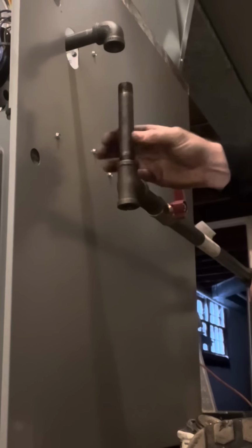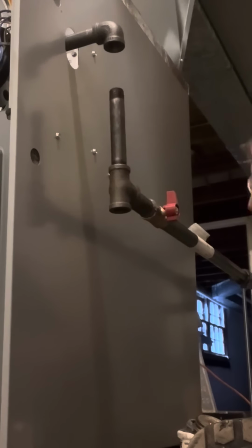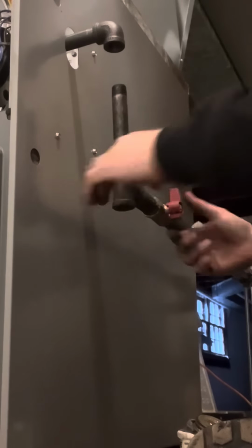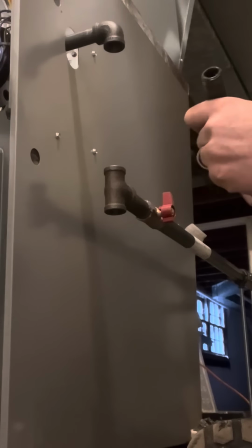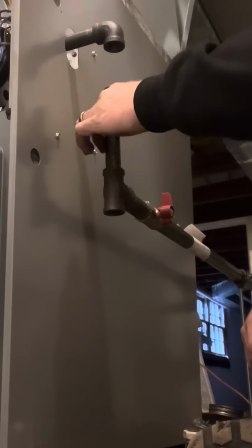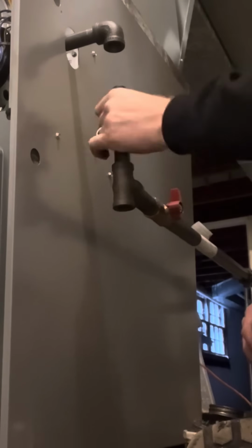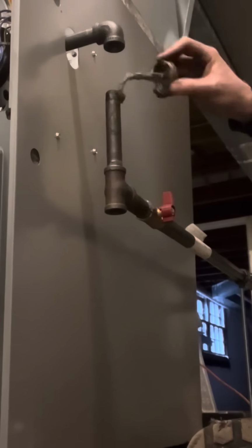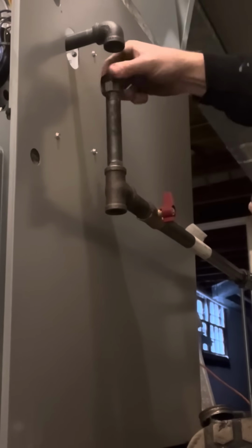Now, on any of these appliances that do require a sediment trap, the code says that it needs to be installed as close to the appliance as practical and after the shutoff valve. Which is a very vague code, because to me, as close to the appliance as practical just means if I have the stuff on my truck to make it work this way, that's the way that it's going in. Because that's just the most practical way to do it. If I have to go to the store, that's just impractical.